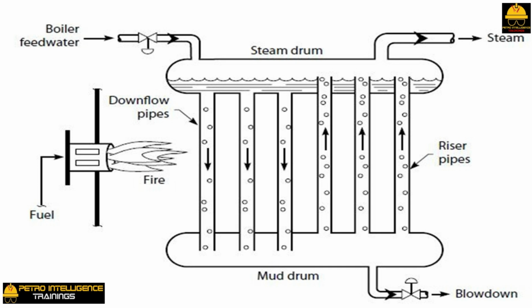The water level in the steam drum in picture controls the boiler feedwater, BFW, makeup rate. However, note that the steam drum is full of boiling water. How can we measure the real level of this two-phase mixture in the steam drum? After all, the external level indication chamber, level troll, holds just water. When we look at the gauge glass, it has water, not steam. Hence, the indicated water level outside the drum is less than the boiling water level inside the drum.